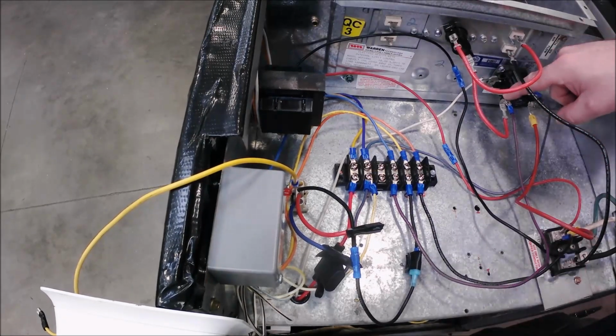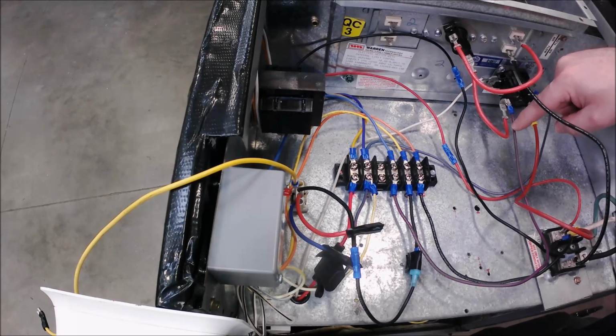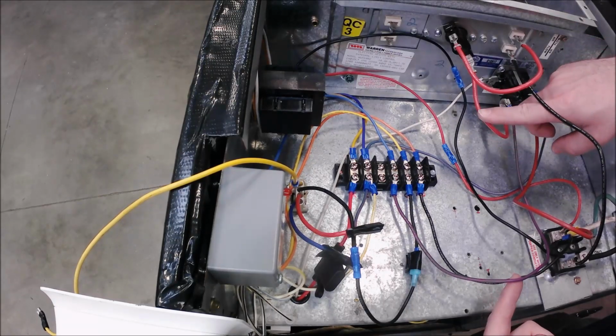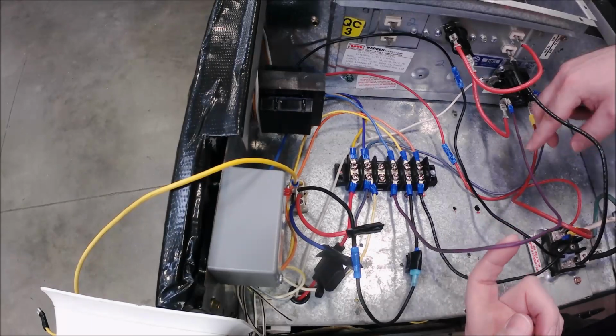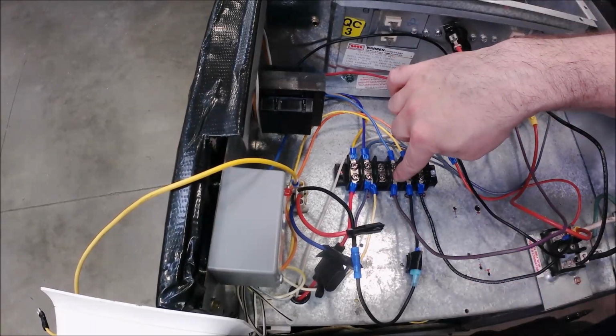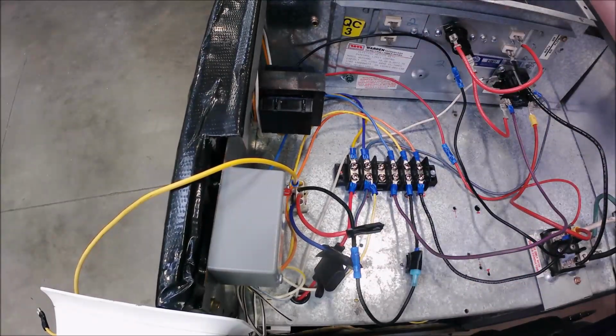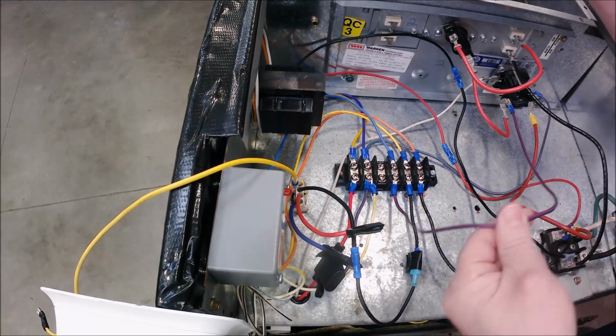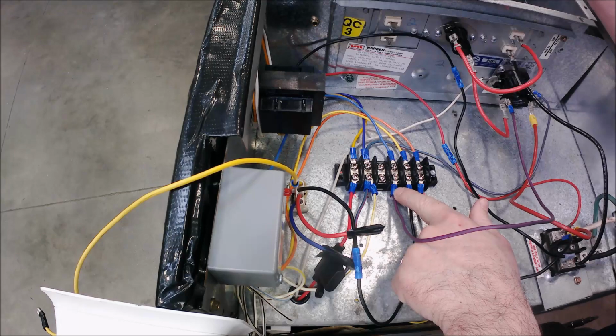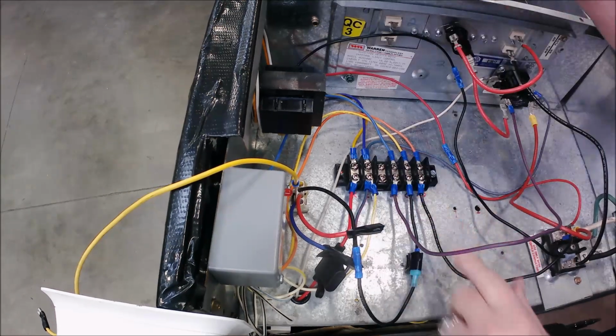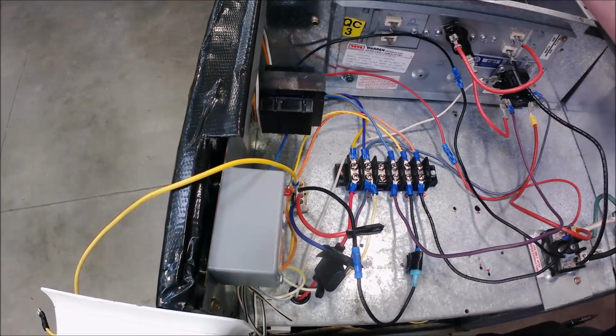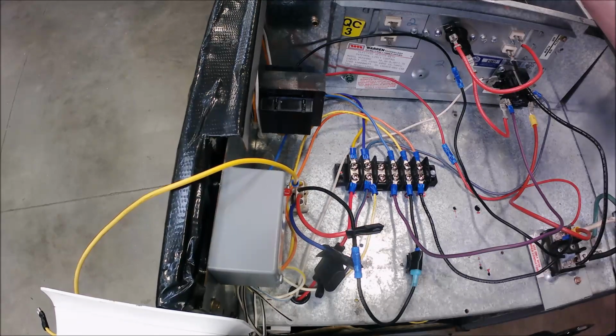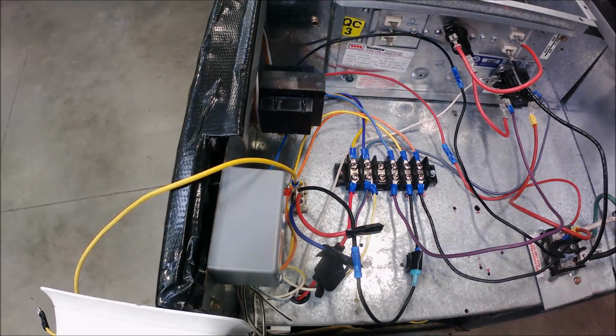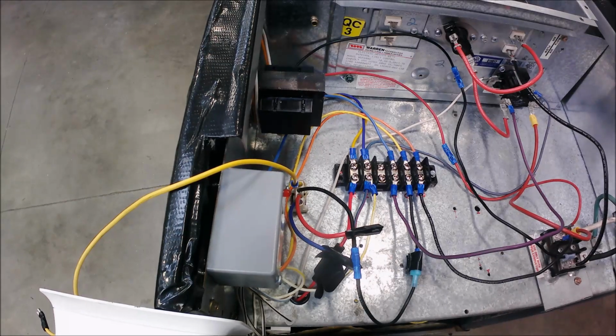So we're going to come out of this sequencer switch to turn on the heater, and we're going to turn on the fan, but we have to use the normally closed connection. There's a lot of thermostats out there that will automatically turn on the fan no matter what, but just in case, we have a normally closed switch on our fan relay that will do that. And honestly, that's pretty much it. I'm going to turn this on and make sure it works, which I'm pretty confident that it will, but we got to double check and make sure.